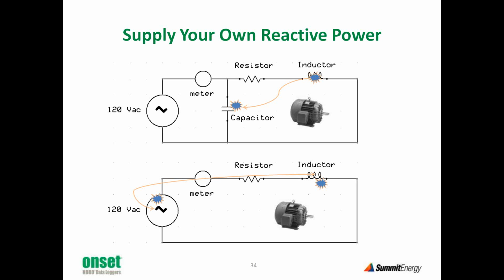So if you're paying a lot for reactive power, you should consider installing a capacitor bank. Now these are typically called power factor correction capacitors, and hopefully you can see now why that would be the case. From the viewpoint of the meter, when the capacitors are there, it looks like the power factor went way up because very little, if any, of that reactive energy is passing through the meter.